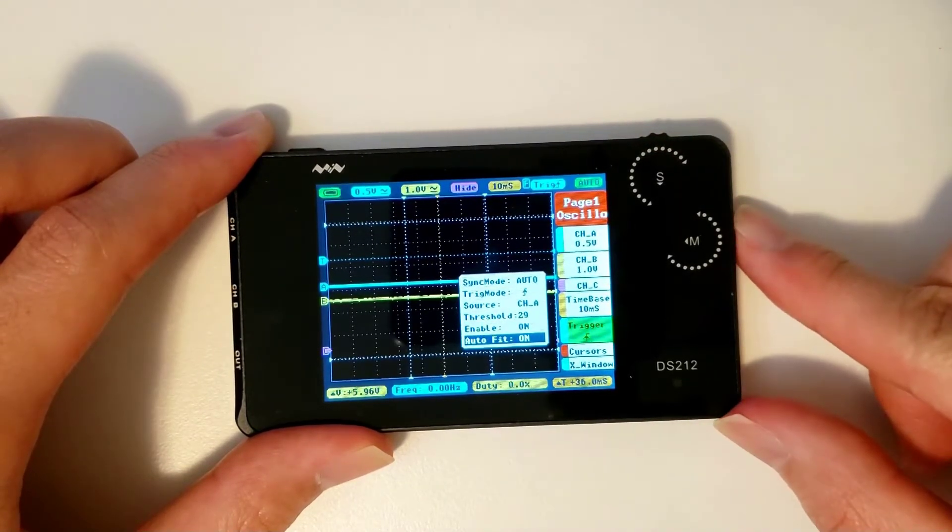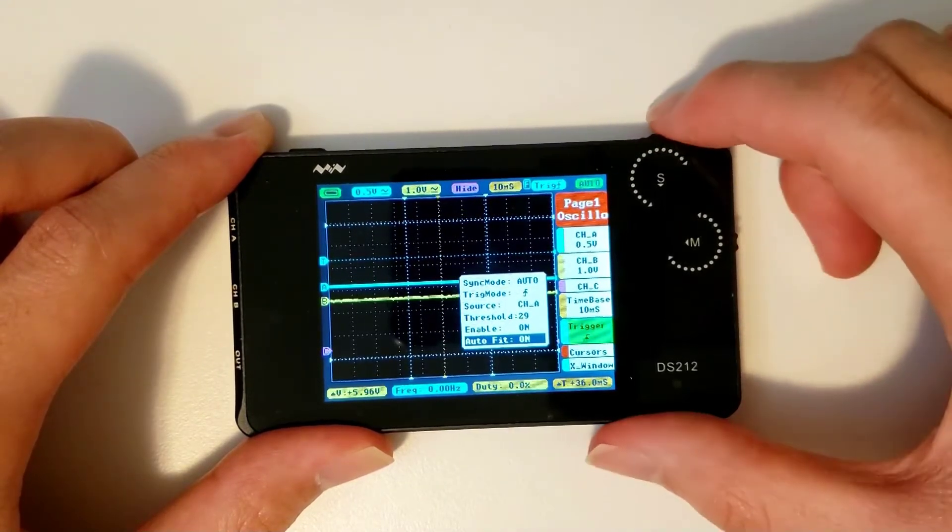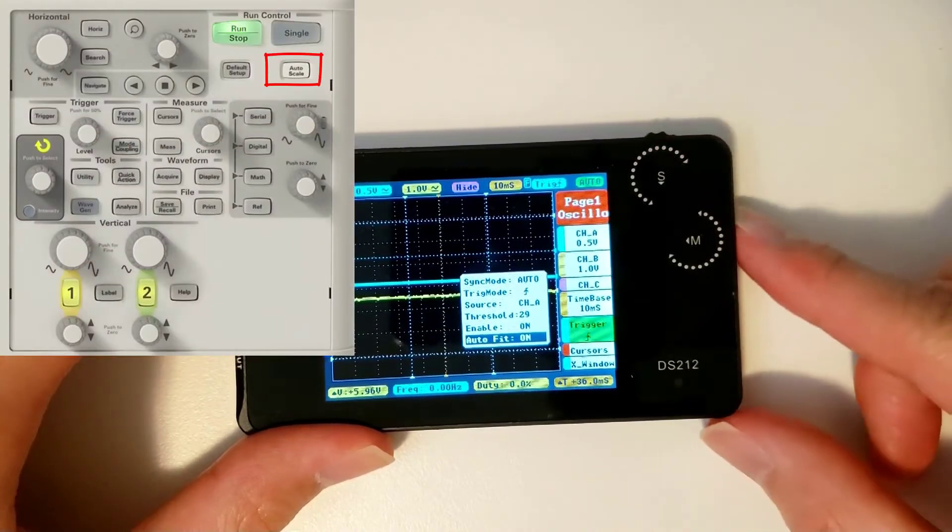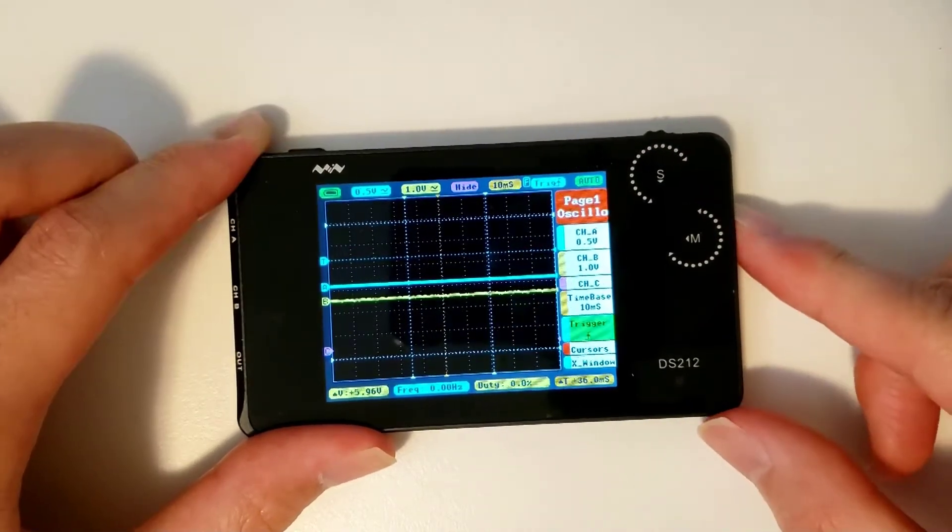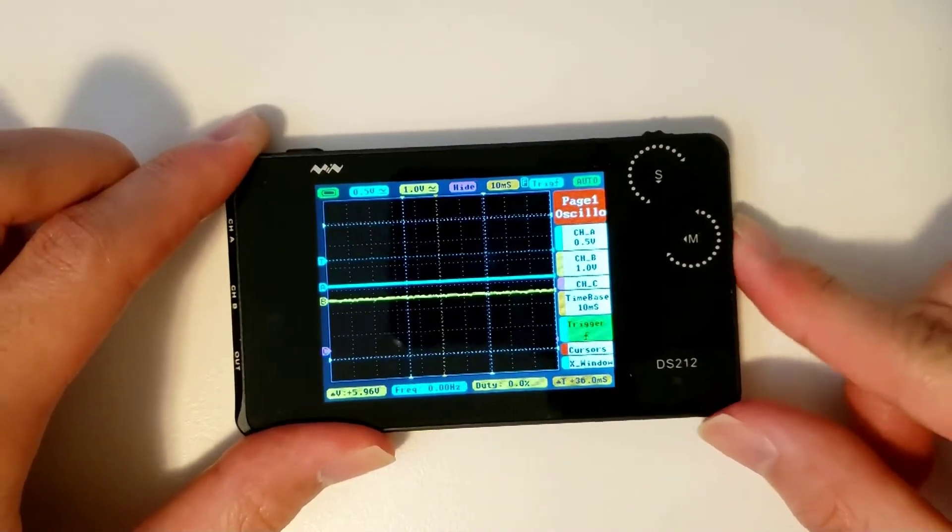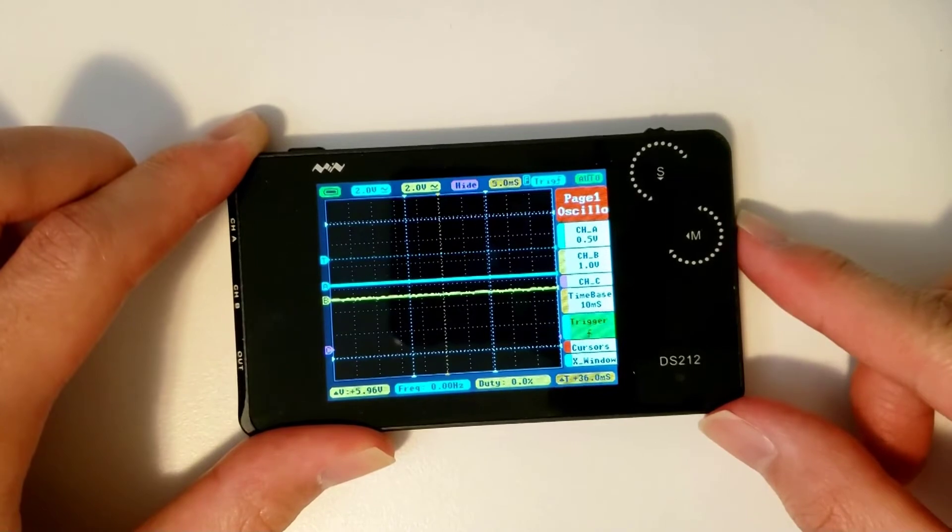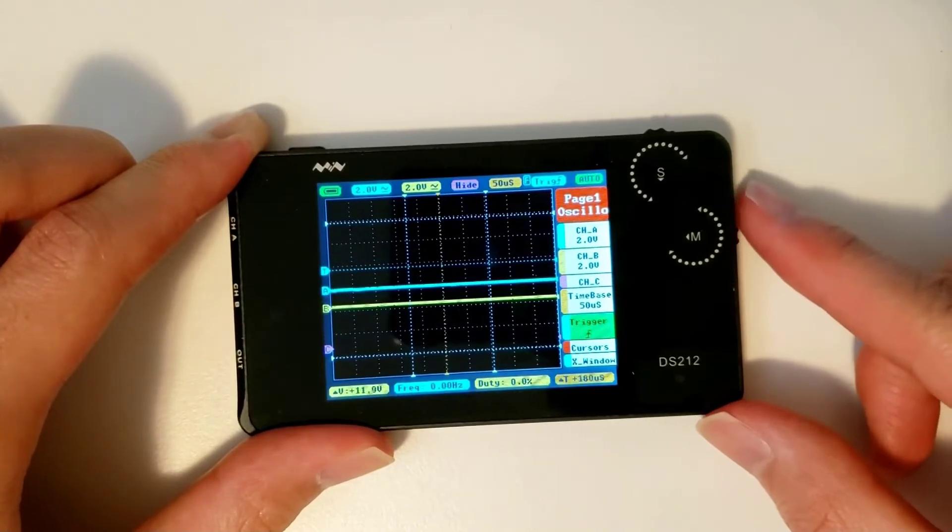The autofit parameter must be enabled before you can use the autofit function. Turn this parameter to on, and double click the M wheel to have the scope automatically trigger the signal.